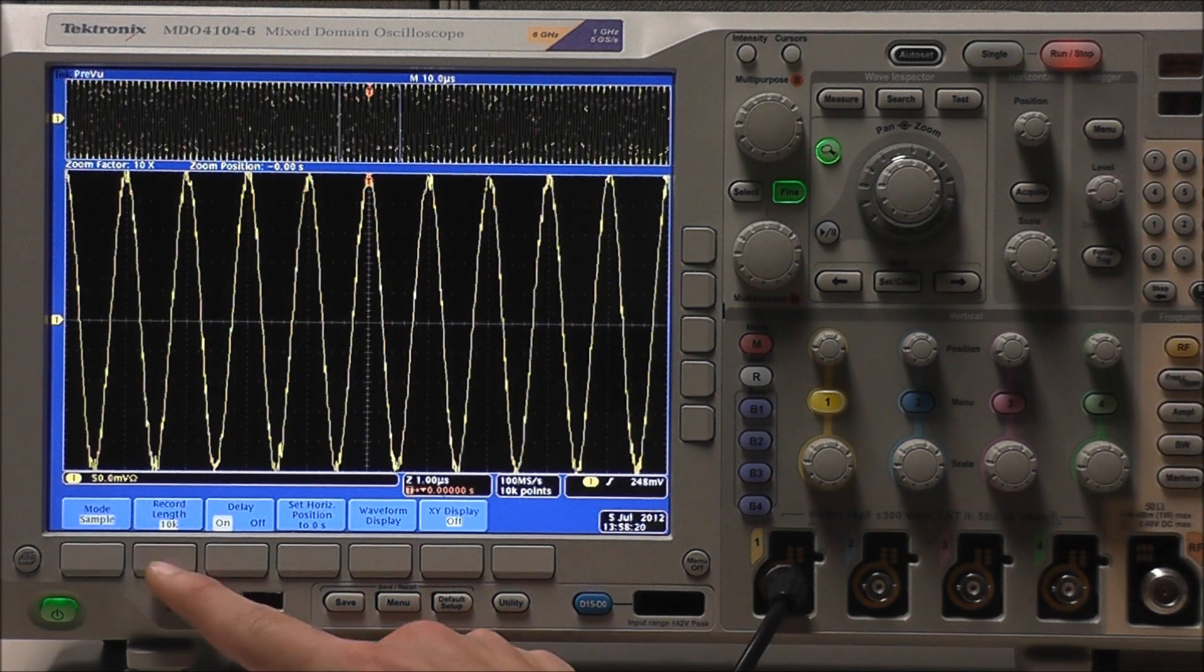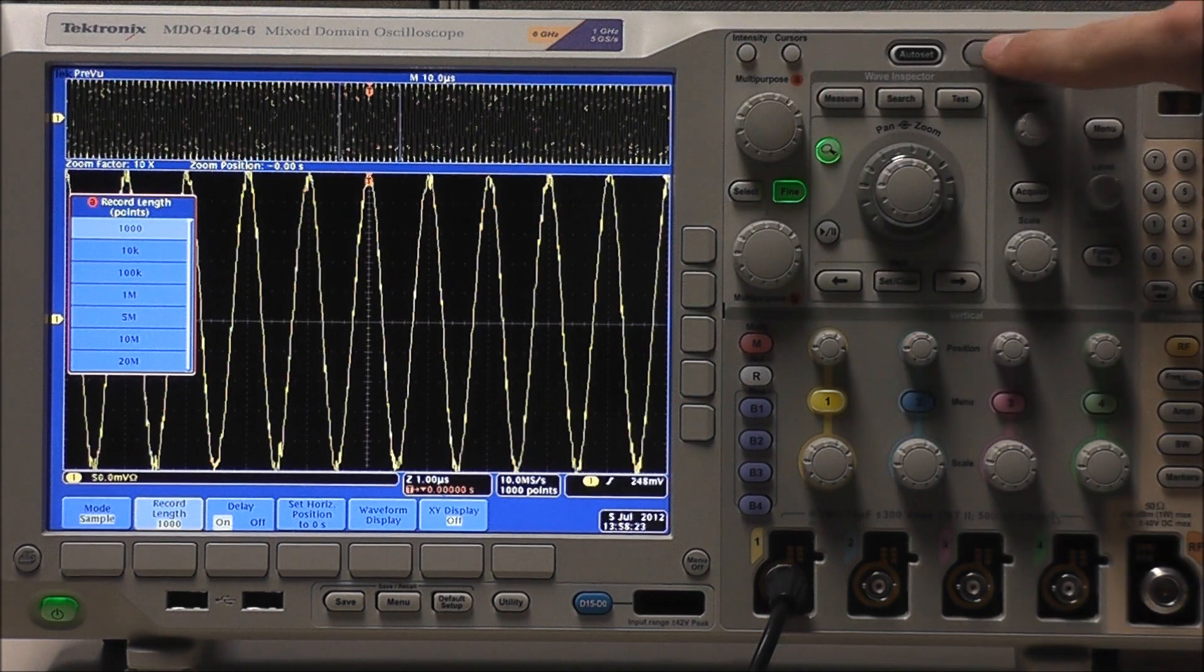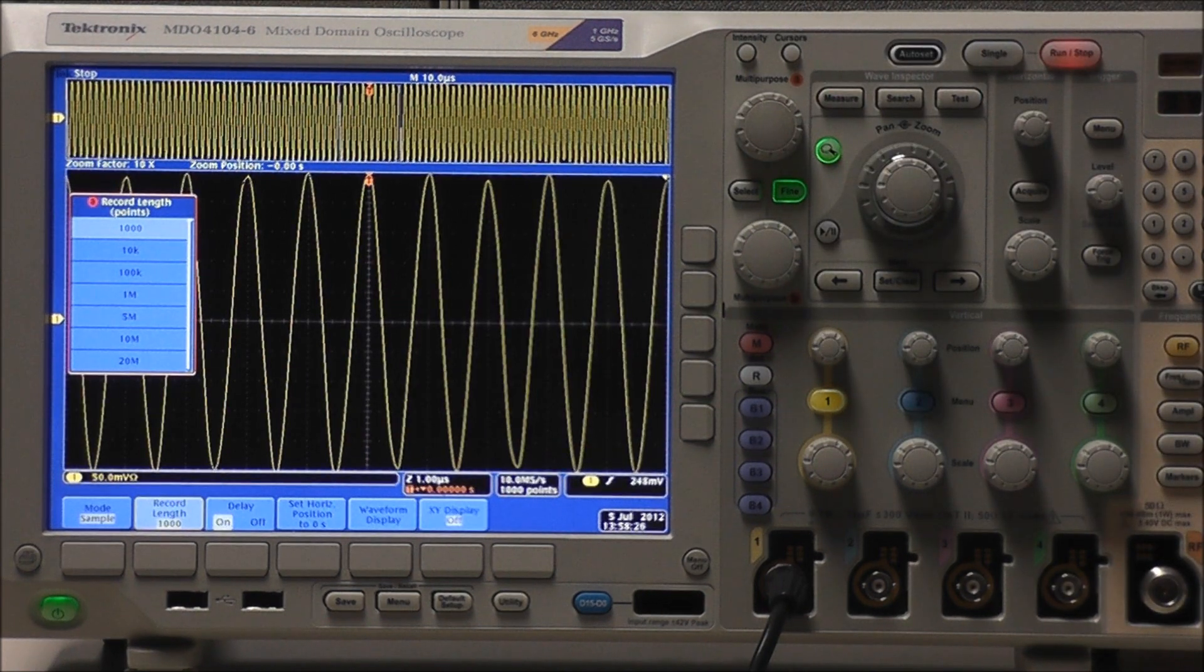Select acquire, record length, and reduce to a thousand in single acquisition. And now we can see how much cleaner and smoother our waveform is.